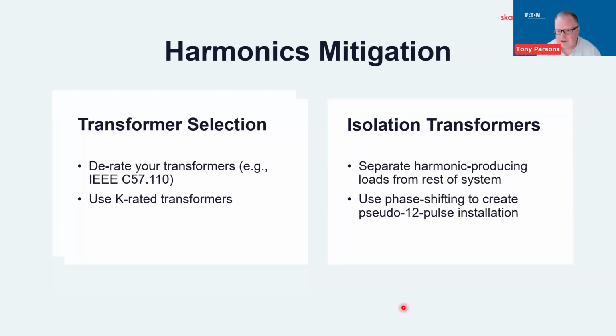And sometimes, again, with the transformers, using isolation transformers. Sometimes it can be used to separate the harmonic producing loads from the rest of the system. We get those isolated on one transformer. We design that to deal with the effects, but then the separation just caused by the impedance of the transformer itself helps the remainder of the system. Or, I've seen it in cases where we have large rectifiers, things like that, use phase shifting transformers, one delta delta, one star delta or Y delta to produce some phase shift that helps reduce, to some degree, harmonics through cancellation further up in the system. So lots of things that you can do if you're dealing with these type of issues.